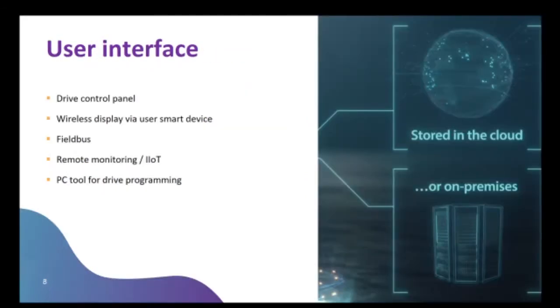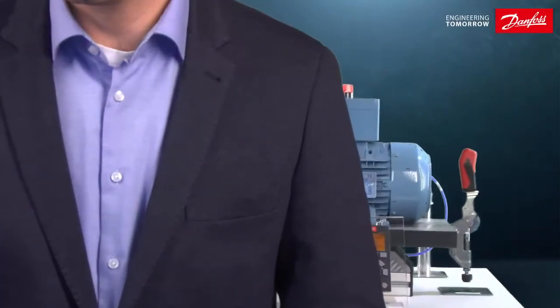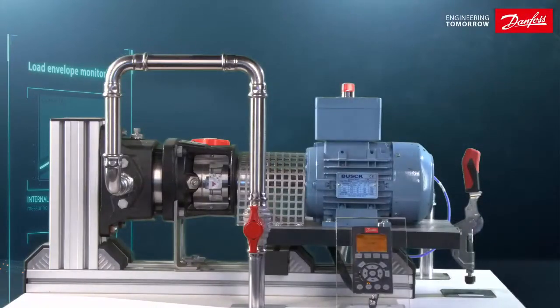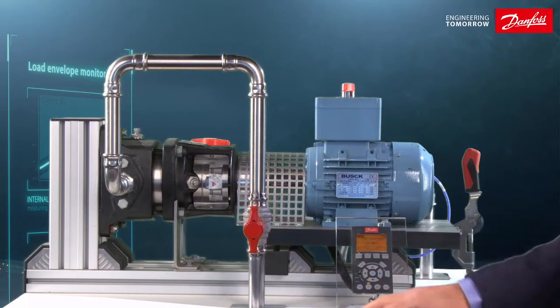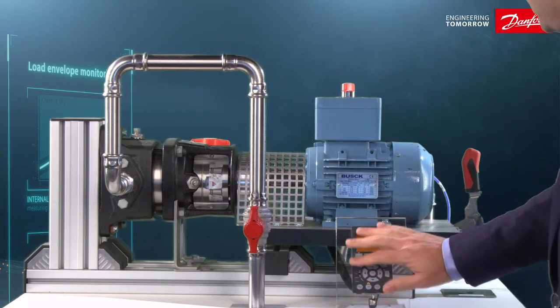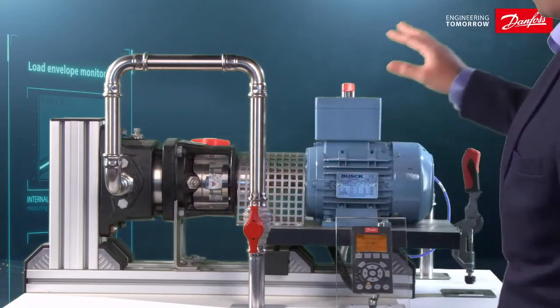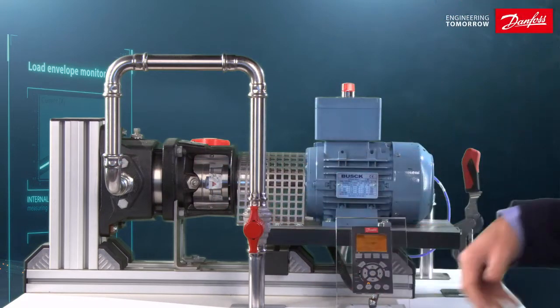Now, once we run the application, we compare the actual value with the threshold, and then we can provide the user information, and that can be provided different ways, through wireless display, through bus communication, or through remote monitoring via IoT. But now I have prepared a very, very short demonstration for you, so you can specifically see how this works. We have a drive, and this is the display of the variable speed drive. We have a motor and a pump. And this setup is specially prepared so we can generate some faults.